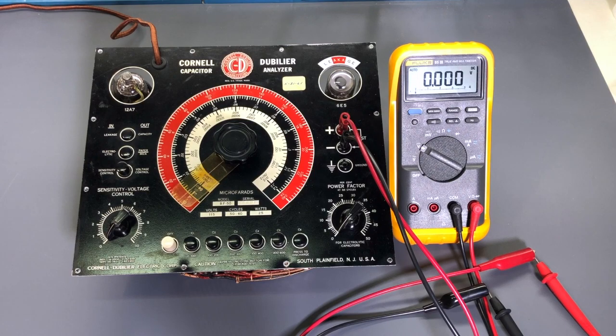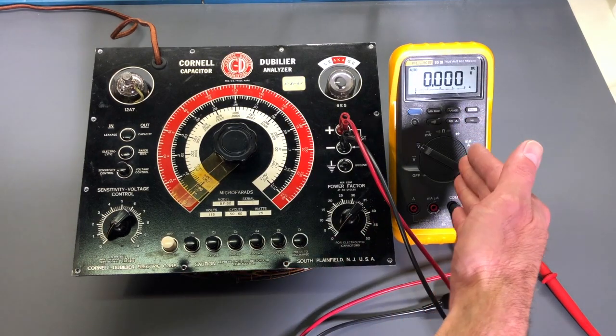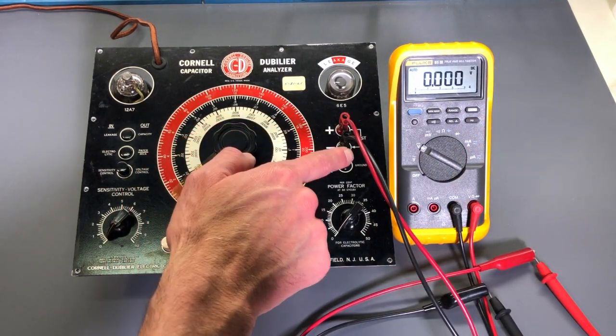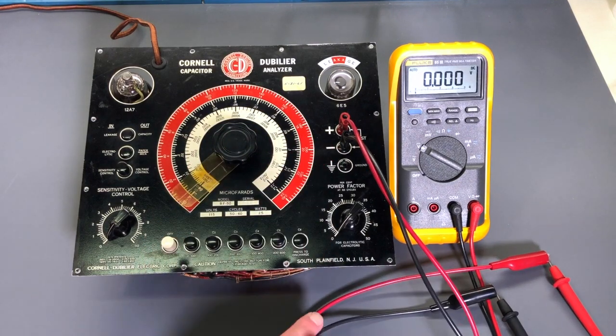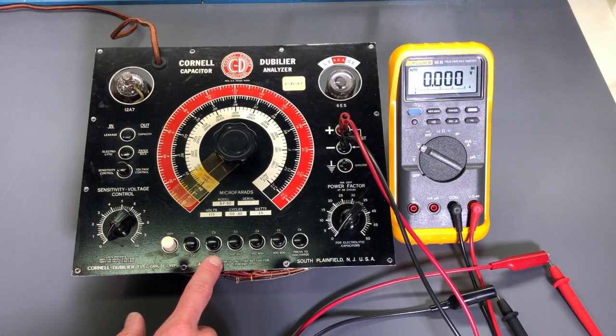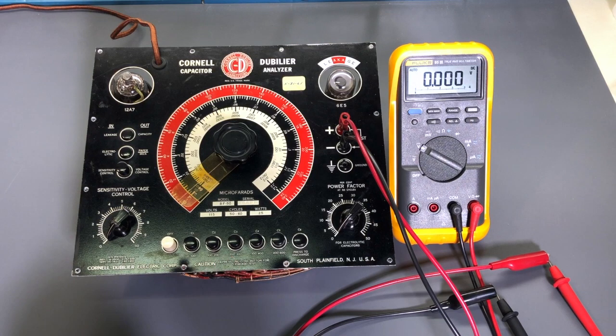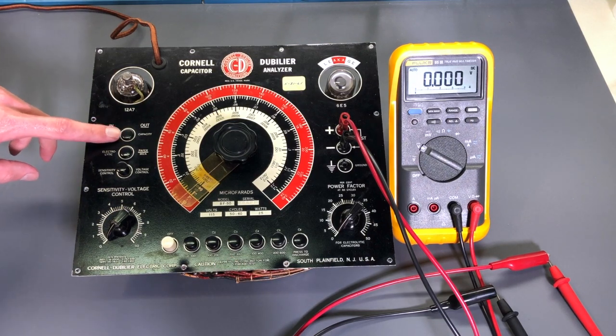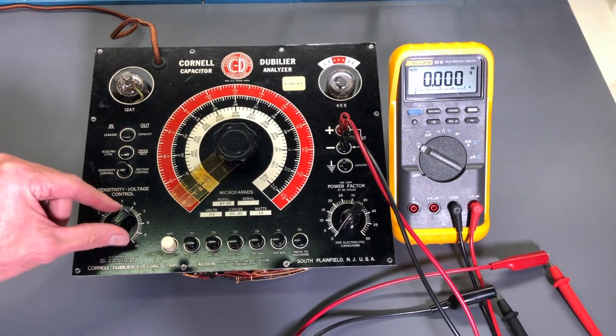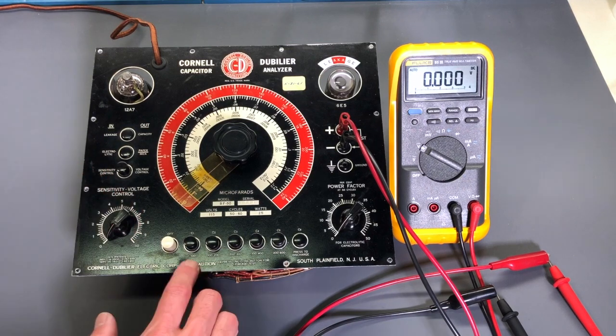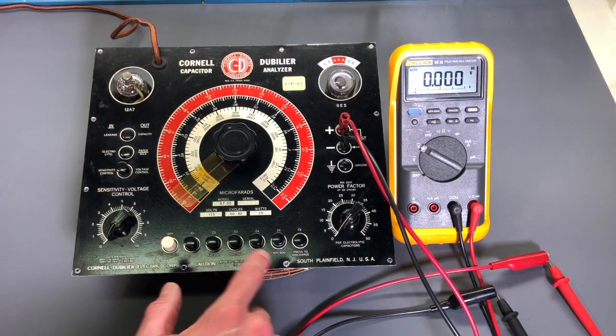Okay, I have the tester positioned with the digital multimeter connected to the test jacks, and we'll see if the voltage ranges look correct for the leakage test. Over here we have it in the leakage mode and the electrolytic mode, and we'll vary this adjustment and see how well that corresponds to these ranges.